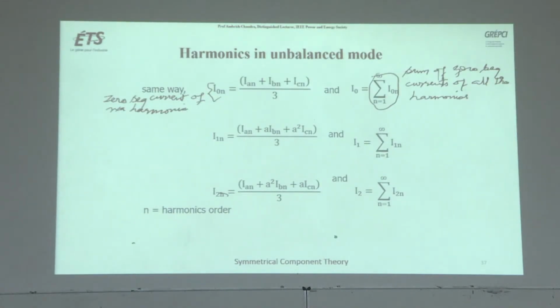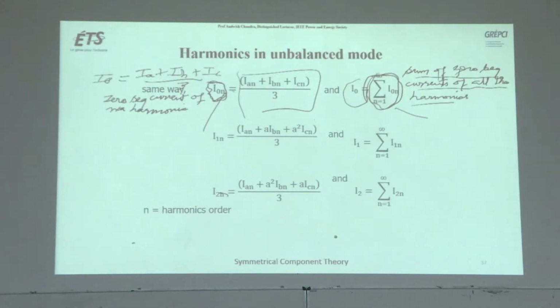Now you can find the zero sequence current of the nth harmonic. This is the same equation we have seen: I0 is equal to IA plus IB plus IC divided by 3. The only thing is that we have put the harmonic here, whether it is fundamental, third or fifth. So the total sum of the zero sequence currents for all the harmonics, you can represent by this. Similarly, the sum of positive sequence currents of all the harmonics, and the sum of all the negative sequence currents of all the harmonics. So this is how you can write it.